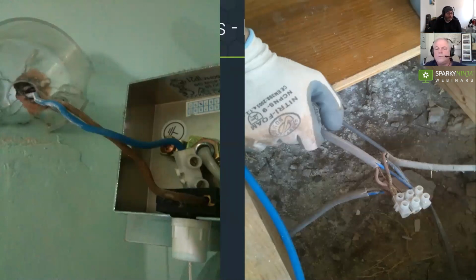Okay. Yeah, and the other thing I think is a comment there. One of the guys has put, people do the same thing but just leave Wagos on there. Think, okay, that's maintenance-free, that's all right, and just leave it open like that. The whole point about putting it in an enclosure is hopefully you'll have some sort of sheath grip on the enclosure to hold the cables in place, so there's no strain on the cables themselves. They need to be enclosed.